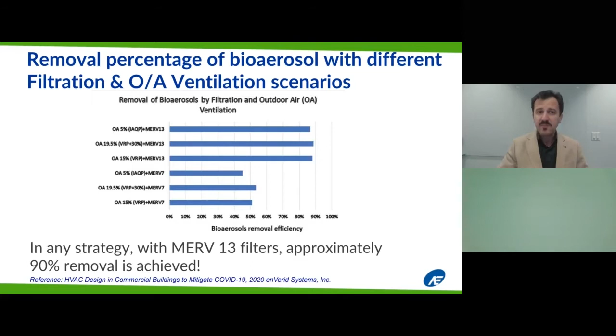Now, multiple studies have confirmed the superiority of filtration over increased ventilation in reducing the transmission risk of airborne viruses. So no surprise that the relative risk of contracting COVID-19 in a commercial building has more to do with filtration strategies than with ventilation strategies. This relative risk can be determined quantitatively using a tool called the Wells-Riley equation. This equation was developed in the 1970s, and it is the most common approach so far for assessing the risk of infection to humans in buildings, by taking into account parameters such as the size of the building, the number of people in the building, the number of infected people, and the amount of time that infected people spent in that building. We can calculate NC, or what is called the predicted number of new cases infected over a period of time in seconds.